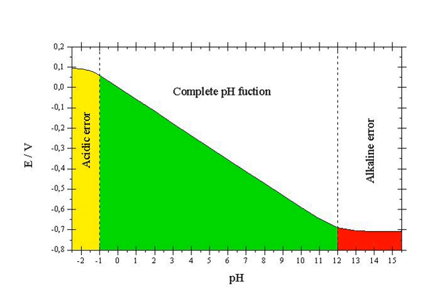Between measurements, any glass and membrane electrodes should be kept in a solution of its own ion. It is necessary to prevent the glass membrane from drying out because the performance is dependent on the existence of a hydrated layer, which forms slowly.